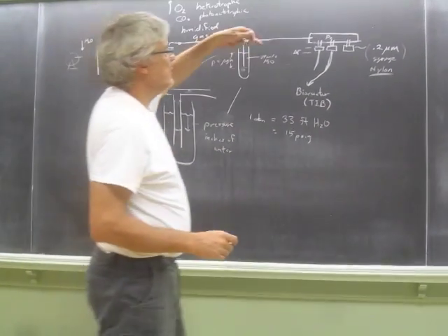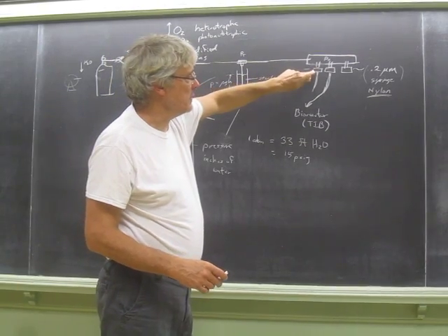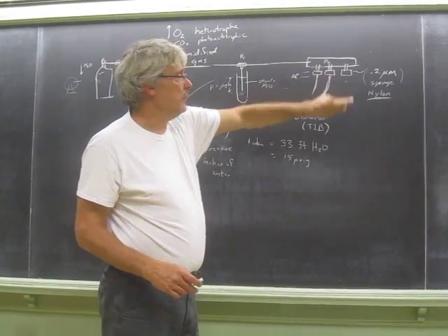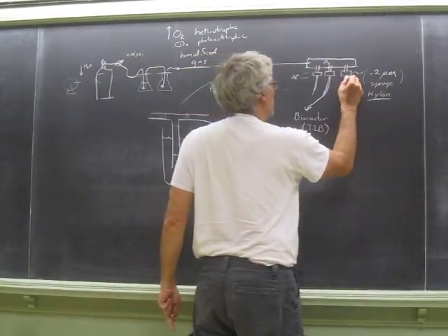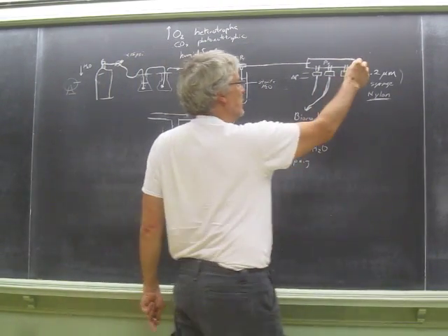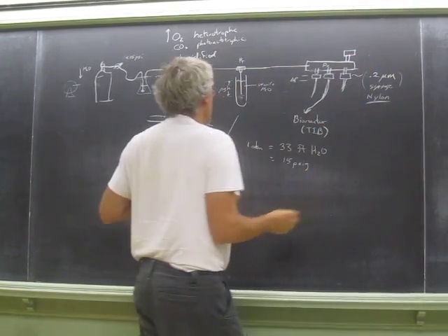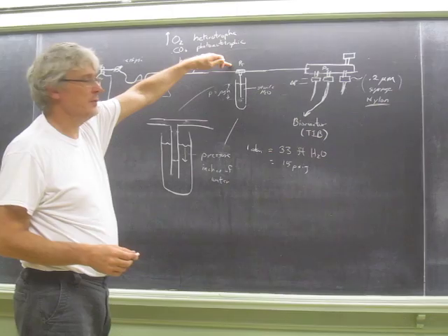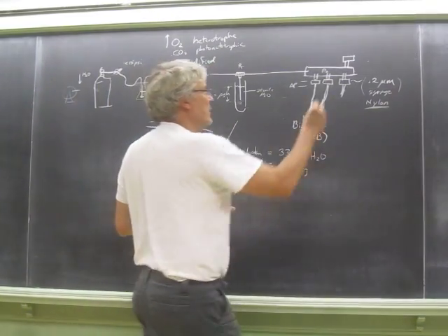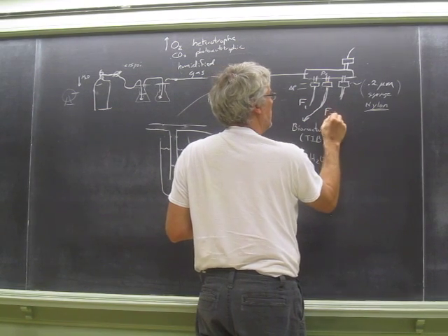So what you can see is that by setting it up so that the controlling pressure is essentially the filters, the same amount of flow rate will come out of each one of those. And if I put another filter on here, as long as my total flow rate into here is high enough to maintain that pressure, then the flow rate out of each one of these is going to be equal.